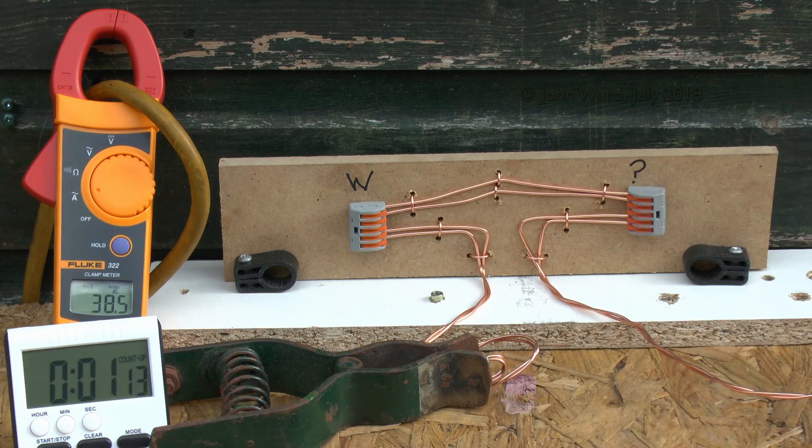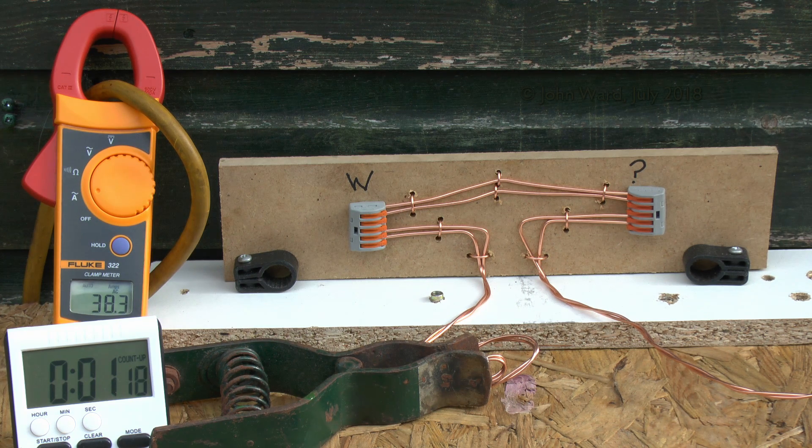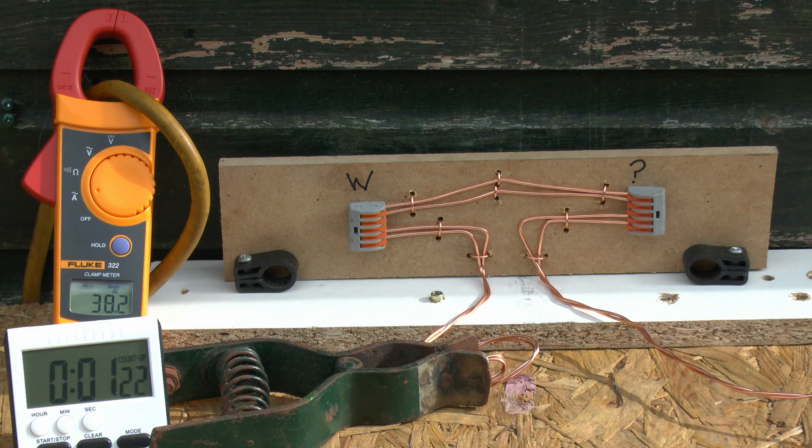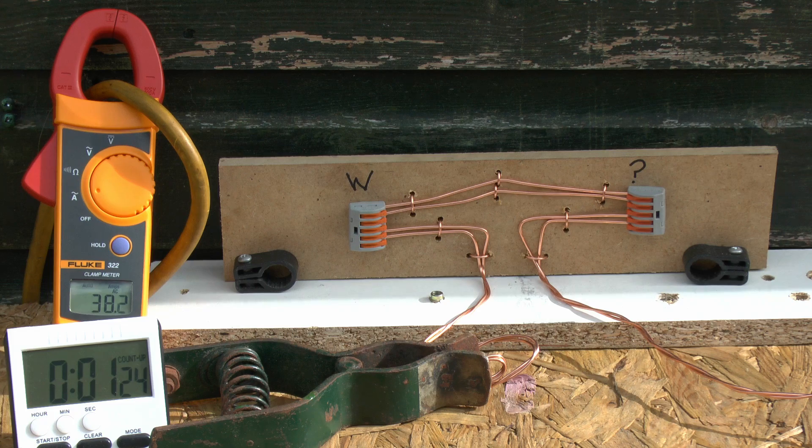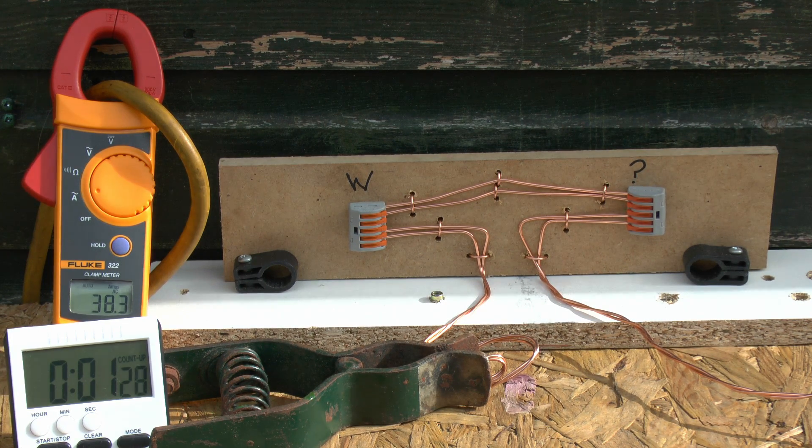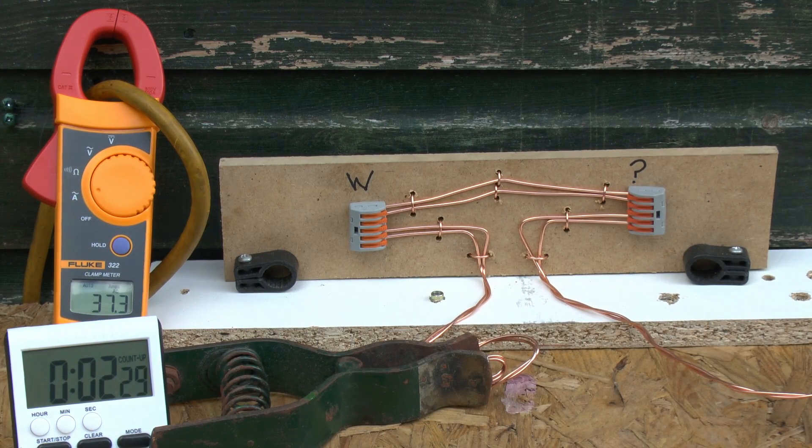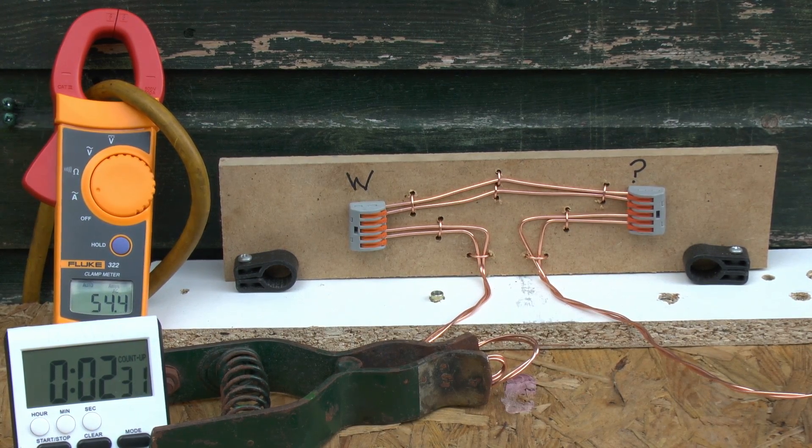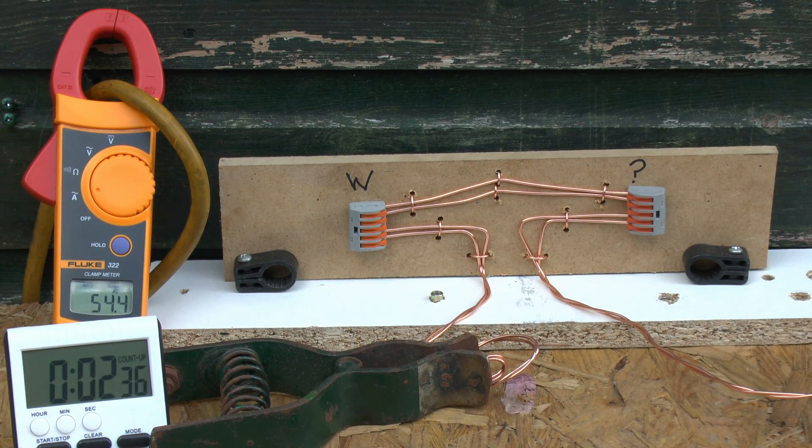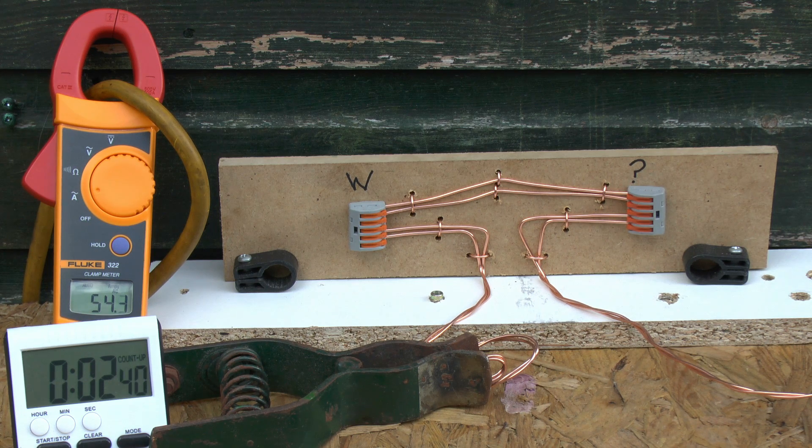So now I've cranked up the current to the next level, which is about 38 amps in this case, and that represents quite a significant overload for these connectors, so we'll leave it running a bit and see if anything happens. So about two and a half minutes in now, and nothing's happening there, so turning up the current even more, so now we're running at around 55 or so amps, or just slightly lower. And again we'll just leave this running and see what if anything actually happens.